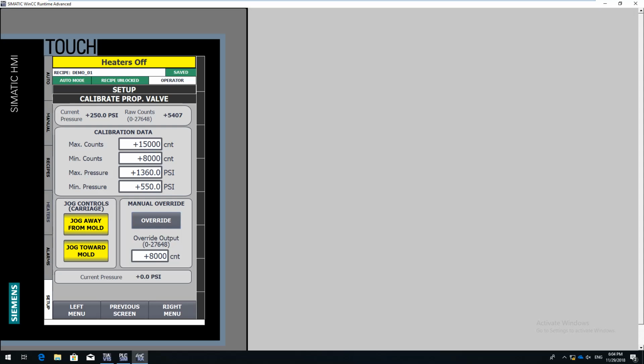Another thing to be aware of for setting up the machine: on our proportional valve, there are parameters. So we actually have to, the first time we power up the machine, pull the cover off of the proportional valve and adjust the high level parameter from 0.1 amps to 0.6 amps, because the proportional valve we buy is capable of moving between 0 and 0.6 amps, which is also tied to our 0 to 10 volt signal out of the PLC. If you do not set that parameter to 0.6 amps, you will not get the full control of what you expect out of that proportional valve.